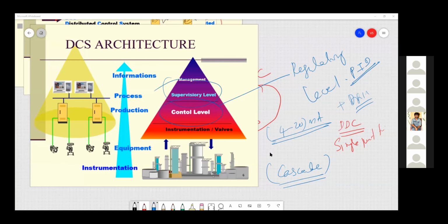It can always be preferred for a long range, but the preference will be 4 to 20 milliamps. The 4 is because of a live zero, dead zero concept. I hope many of you know this. So, to retain a linear range, there is a 4 to 20 span, that's why they use a 16 milliamps span.